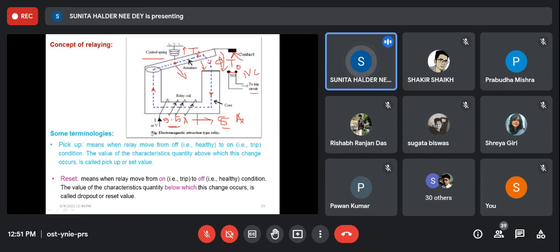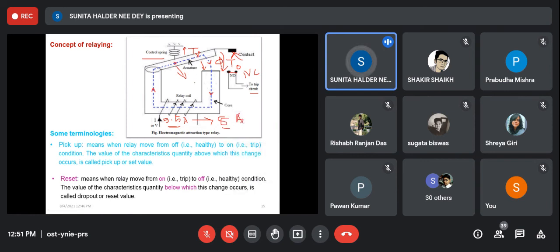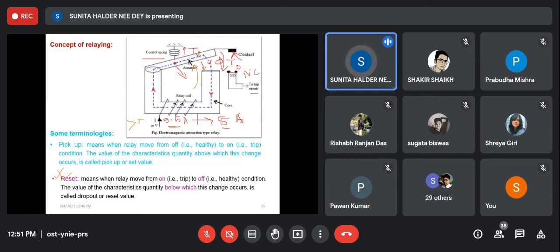Similarly, there is reset. Reset means when the system is healthy again and the current goes back to 5 ampere or less than 5 ampere, then what will happen? Again it goes towards the rest position, and that is called reset. That means when the relay goes from the on condition to the off condition, or from the closed condition to the open condition of the circuit breaker or the relay, it is called reset. Ideally, if the relay starts operation for current greater than 5 ampere, it should reset for any current less than 5 ampere. But this does not happen for this particular type of relay. Why? Because an air gap is involved here.